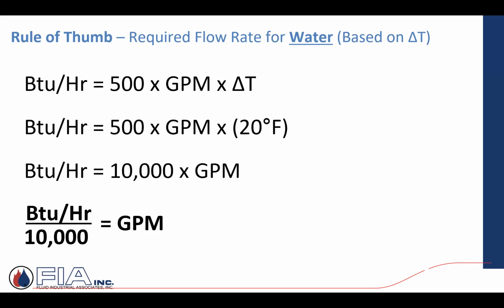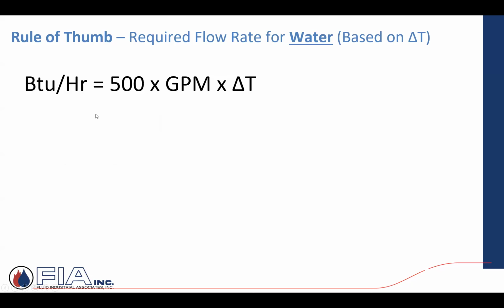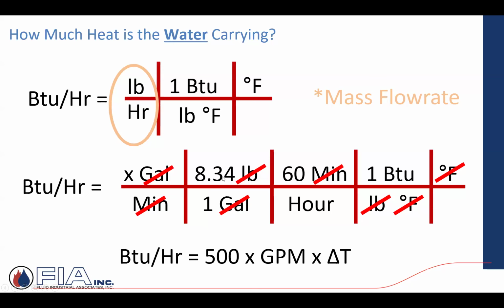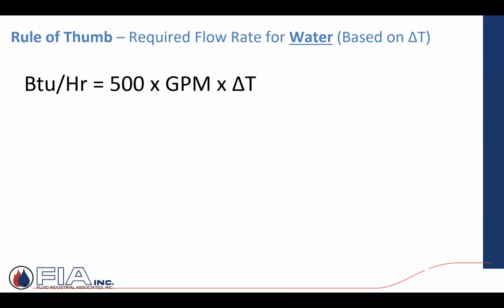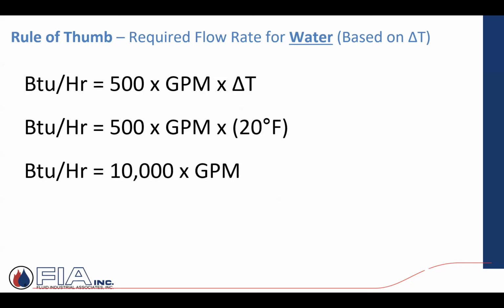So BTUs per hour. Now the 500, where's it coming from? Quite simply, 8.33 or 8.34 pounds per gallon times 60 minutes in an hour, because we're talking BTUs per hour, but our flow rate is measured in gallons per minute. So I take that 8.34 times my 60 minutes, there's my 500. In this case, when I apply that number, I say 500 times my delta T, my change in temperature, 20 degrees, 10,000. That becomes my factor.